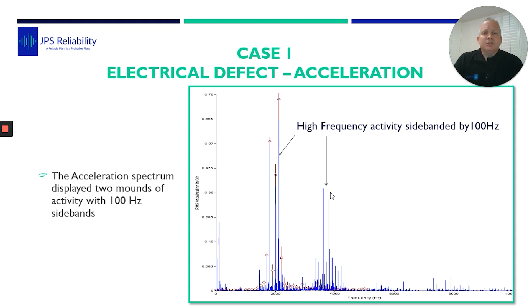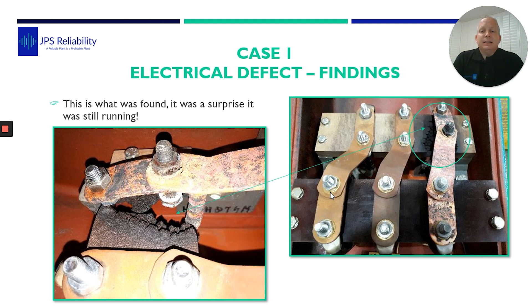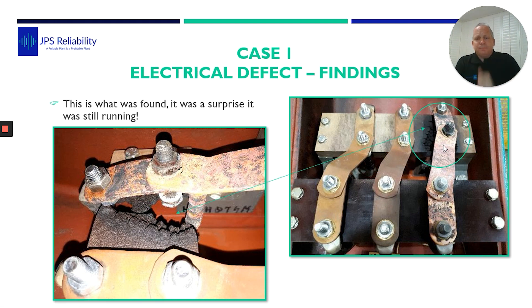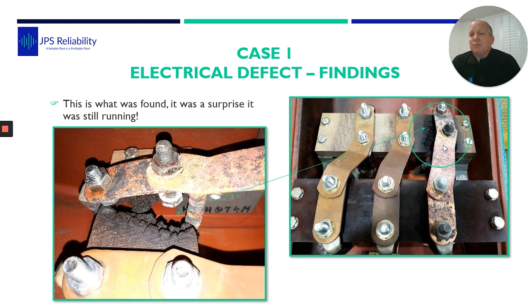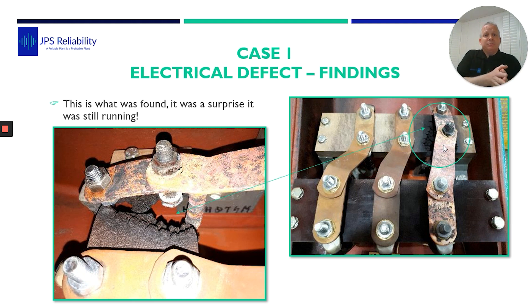Something connection-related. And the recommendation was to check all the terminations. So they took the terminal box off and found that one of the phases had got a little hot. I asked them how long the motor had been in — only three months. So straight away you think: why did that connection go bad in three months? It was great that vibration picked this up, but you had to use your human senses and a bit of common sense to work out what component was actually causing the issue.